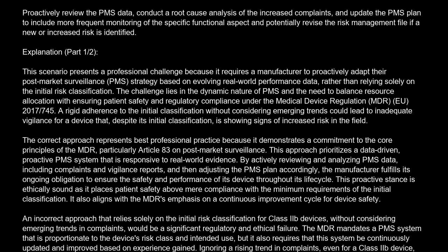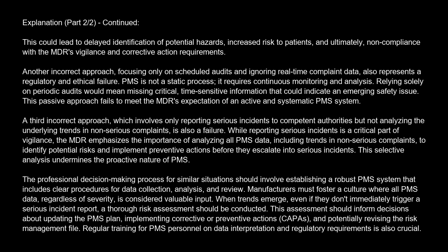An incorrect approach that relies solely on the initial risk classification for Class IIb devices, without considering emerging trends and complaints, would be a significant regulatory and ethical failure. The MDR mandates a PMS system that is proportionate to the device's risk class and intended use, but it also requires that this system be continuously updated and improved based on experience gained. Ignoring a rising trend in complaints, even for a Class IIb device, suggests a failure to implement an effective PMS system as required by Article 83 and Annex III of the MDR.